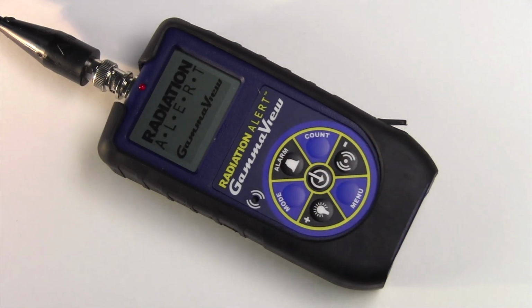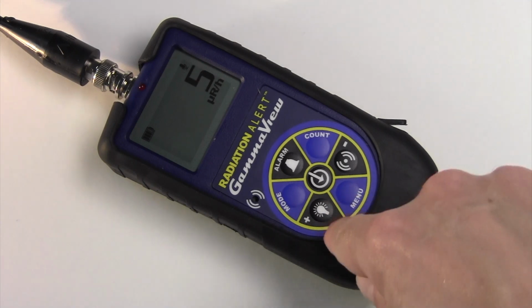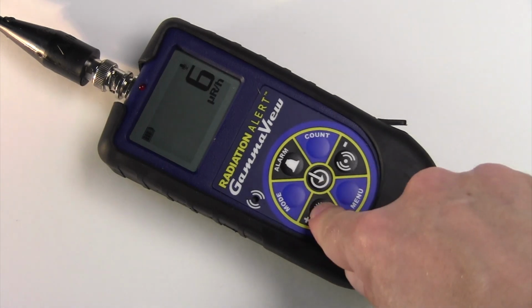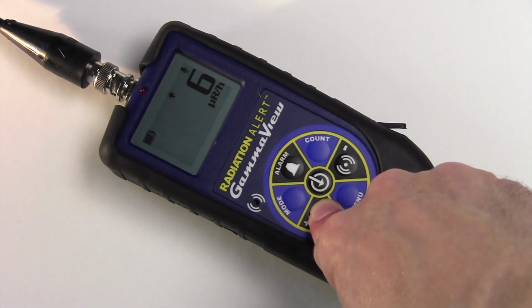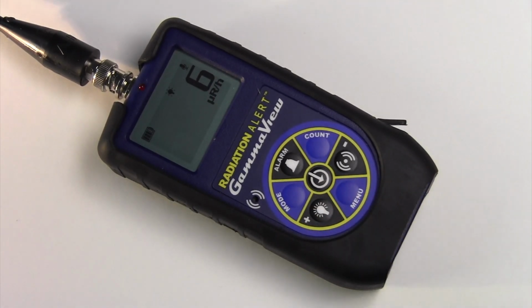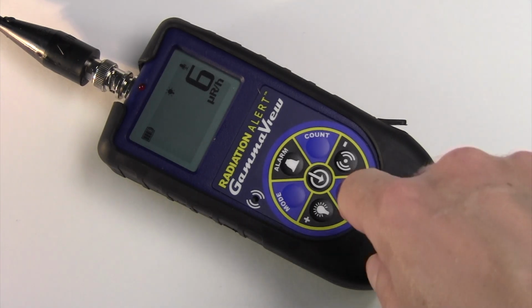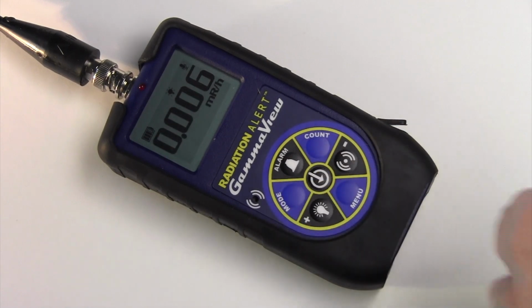The screen displays the system information and icons. After boot up, we can press the light control to illuminate the display. Hold the control for a few seconds to keep the light on, if you wish. The display is in microroentgens per hour, which can be changed easily. Press the mode control to switch units.